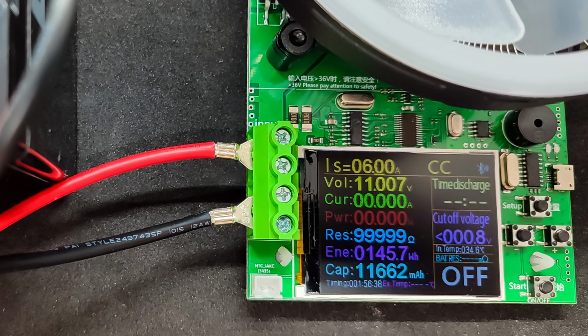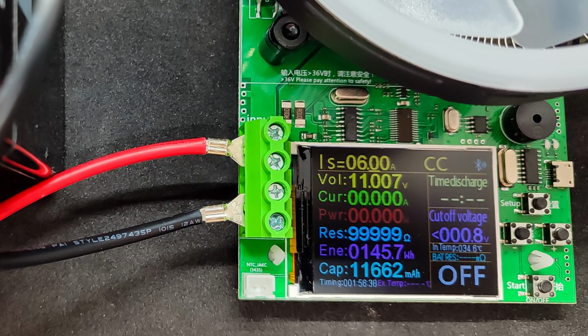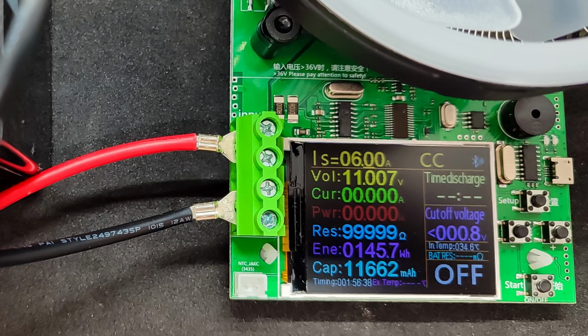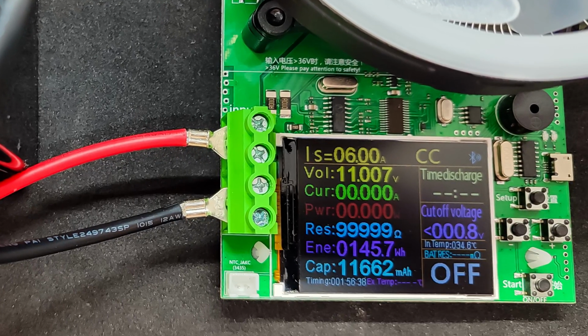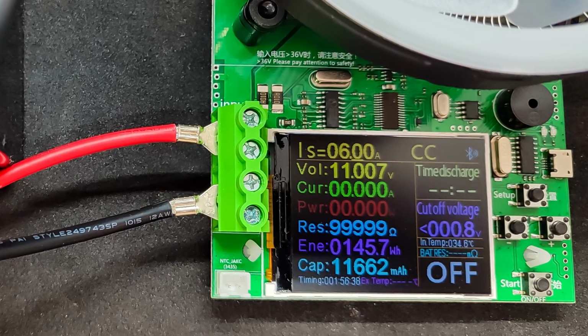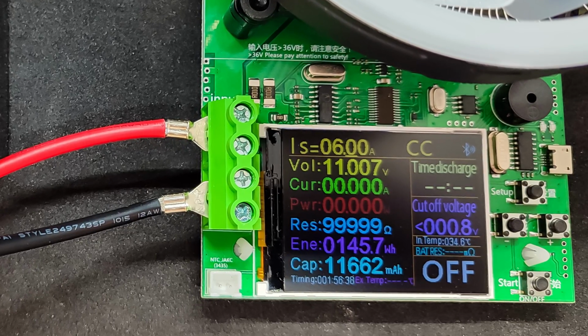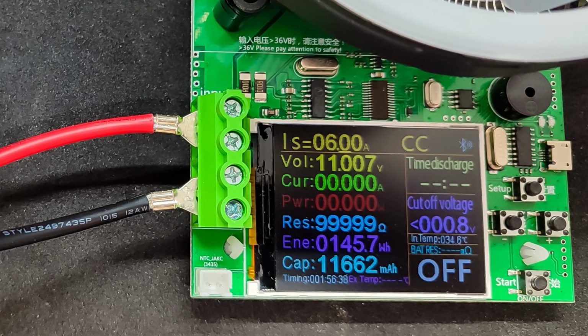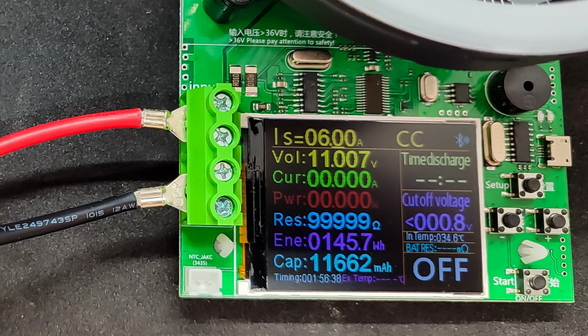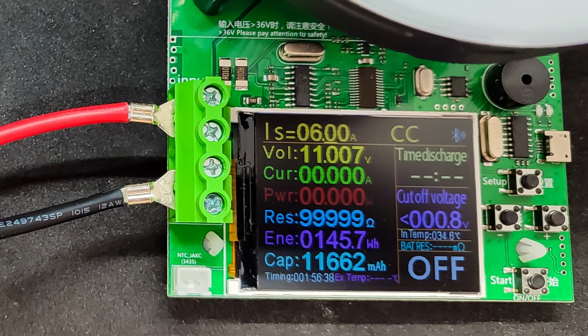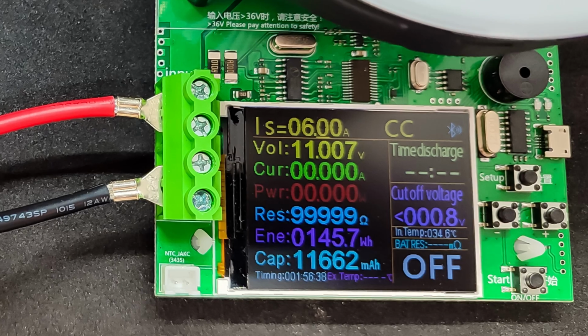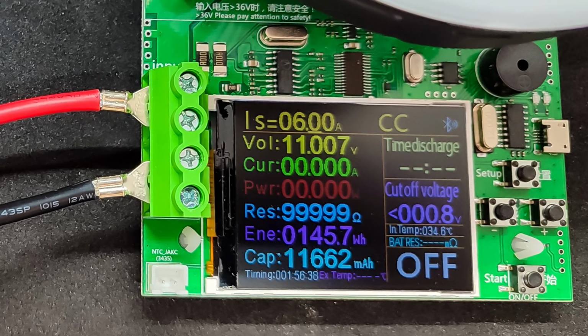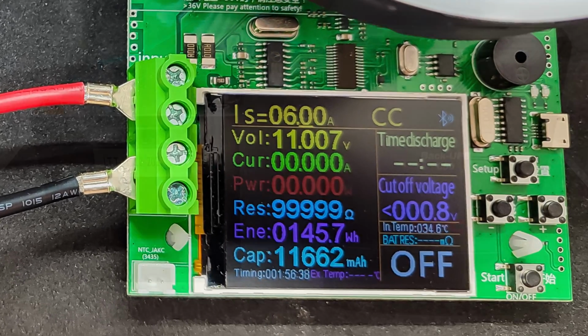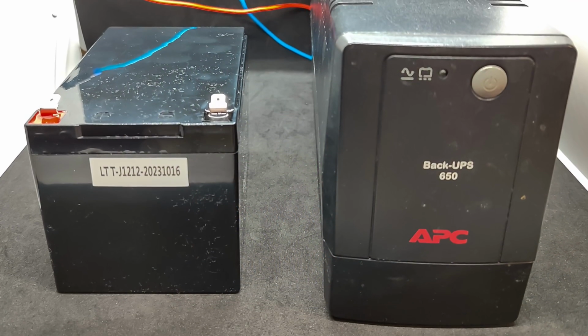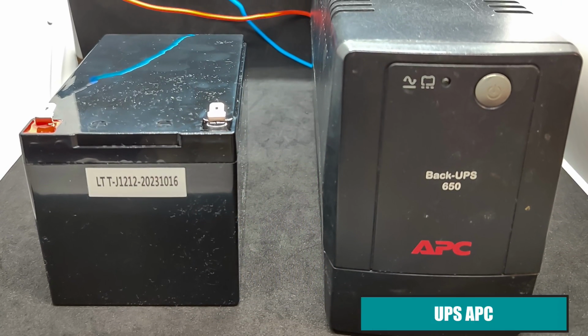After some thought, I came to the conclusion that in the case of use with an uninterruptible power supply, this is rather good. Because the UPS itself disconnects the battery at low voltage, according to my information, somewhere around 10.7 volts. But if the BMS had disconnected the battery at 11.2 volts, it would have been an abnormal situation for the UPS, similar to if its battery was suddenly removed during operation. Now it's time to see how the uninterruptible power supply will react to this assembly.